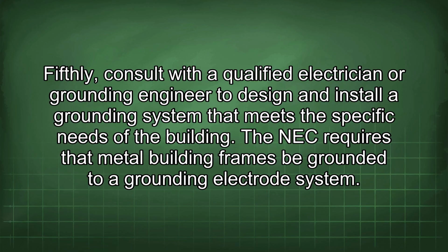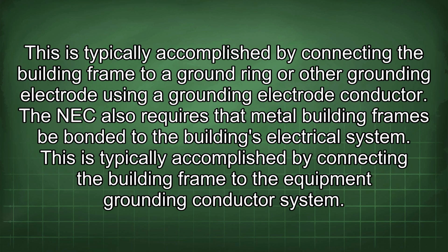The NEC requires that metal building frames be grounded to a grounding electrode system. This is typically accomplished by connecting the building frame to a ground ring or other grounding electrode using a grounding electrode conductor. The NEC also requires that metal building frames be bonded to the building's electrical system. This is typically accomplished by connecting the building frame to the equipment grounding conductor system.